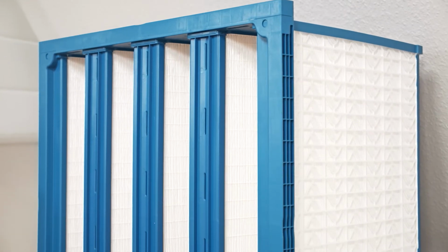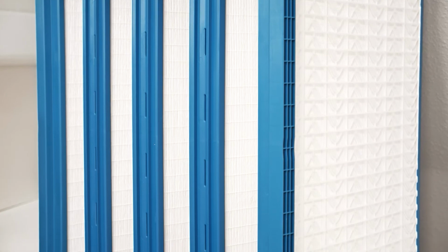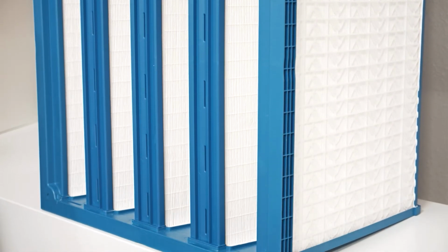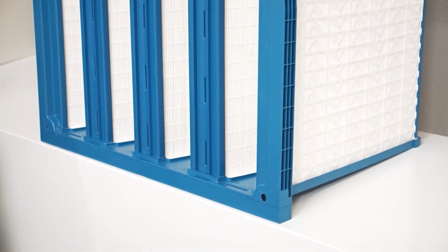Unlike ISO 16890 or ISO 29463, which focus on general HVAC applications or cleanroom applications, the new Part 1 of ISO 29461 is a standard that is tailored to the needs of the gas turbine industry. It applies higher air volume flow rates, higher pressure drops and different filter shapes typical to gas turbine applications.